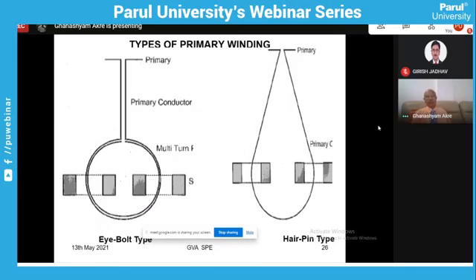These cores are actually at the bottom level. They are at the bottom level, that means they are in the tank which is connected to earth, and that is why it is called a dead tank design. Now the primary is at very high voltage from the top, for example say 66 kV. Then this primary will come to the bottom, that is at ground potential, and it will take a loop across the secondary as a primary winding and go.